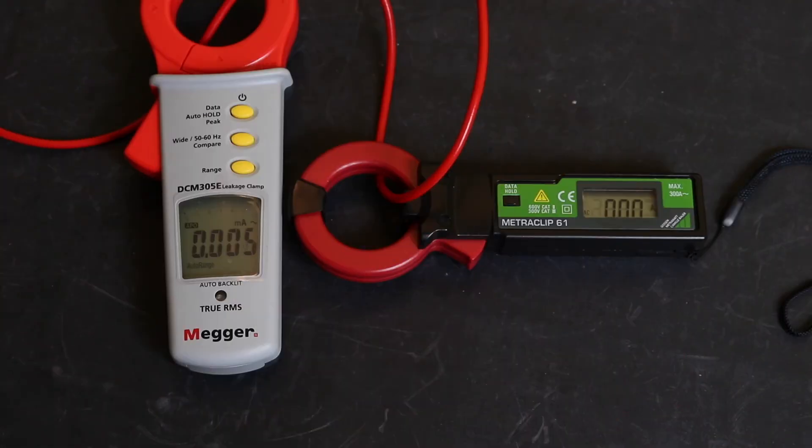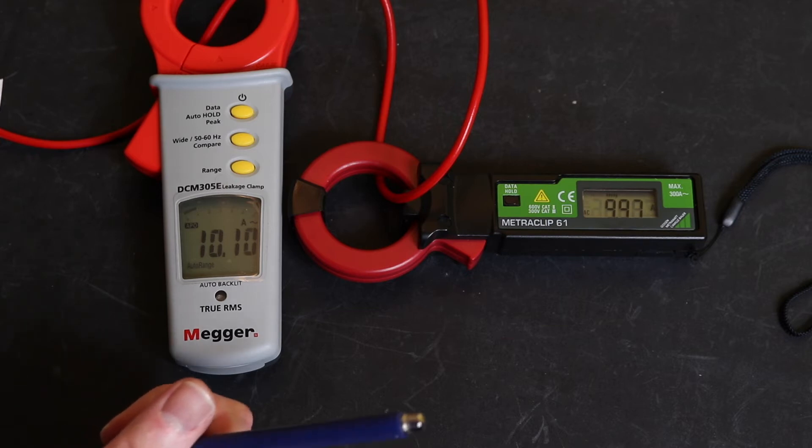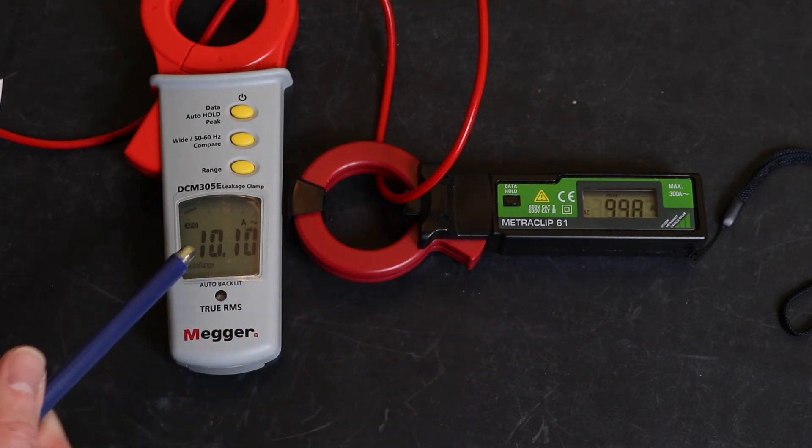Okay so we'll take a look at some intermediate readings here. We'll start at 10 amps on them. We're going to go down now. That Gossen really is a poor display to read. It also does vary a little bit whereas Megger does seem quite a bit steadier.